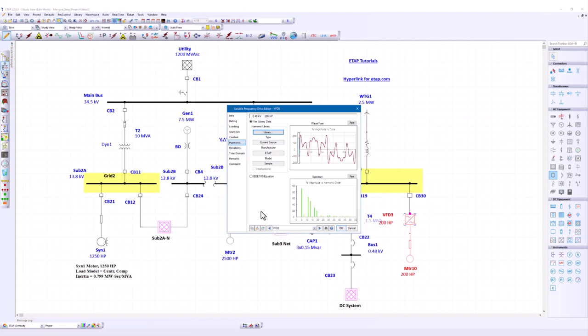There is another way that you can create characteristic harmonic waveforms. That is by selecting the IEEE 519 equation option. And here you can specify the parameters, for example, number of pulses, the shift angle, alpha, parameter XC, beta, maximum order. So ETAP is able to automatically populate the waveform and the spectrum based on the parameters you enter.